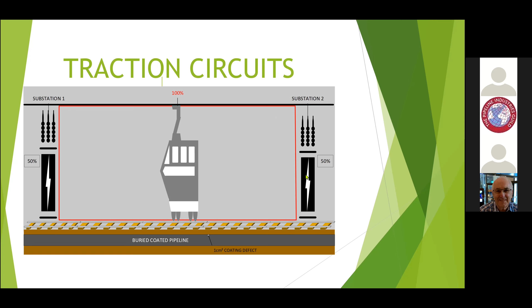But the thing to note is that this coating defect is receiving the current all the time, the effects of the current. Although that current will be changing in some way, it's under the influence of that interference all the time. So it's not right to say it only suffers from interference for that 6 milliseconds when the train goes by. It doesn't. It suffers from it all the time until the train moves into the next segment and it picks up its power from this and the next substation along the line.